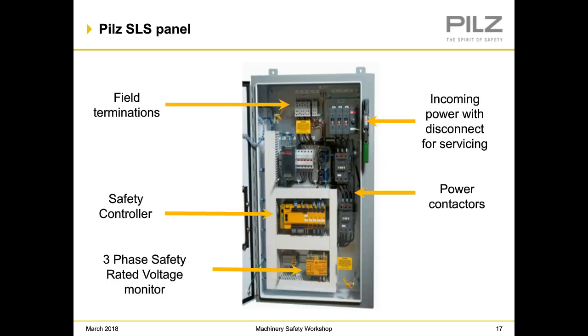So this is what the SLS panel looks like, a picture of one, and what's inside it. You'll see you have field terminations, and then you have an incoming power disconnect. Now this disconnect here is only for servicing, so it's not turned on and off every time the unit's cycled. That's the power contactors that are below that that are turned on and off each time the unit's cycled. You have a safety controller, and then we have a three-phase safety rated voltage monitor, and that's called the PU3Z. So that's essentially what's inside a safety lockout system.